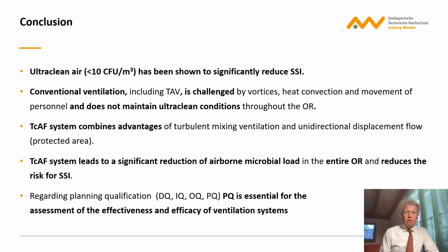Temperature-controlled airflow systems combine the advantages of turbulent mixing ventilation and unidirectional displacement flow. So you have a protected area, but you maintain and manage the ventilation in the entire room.